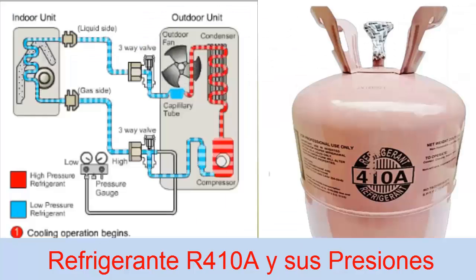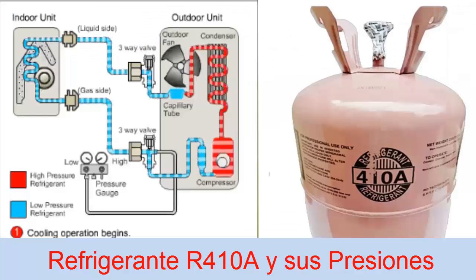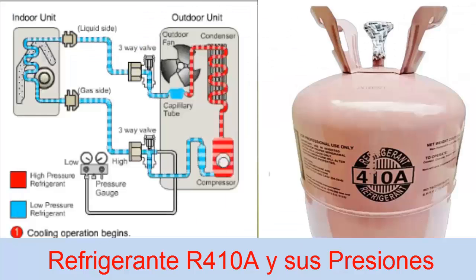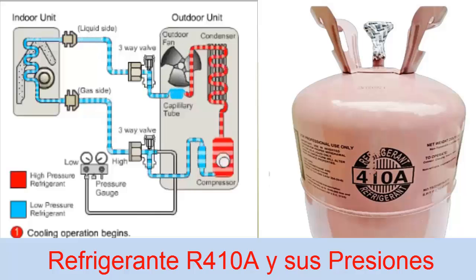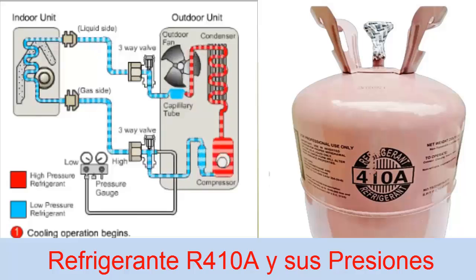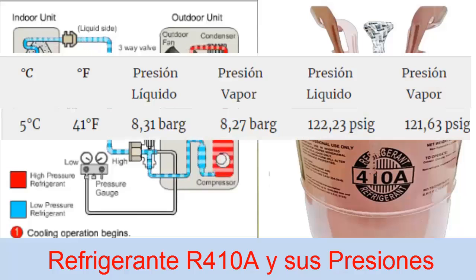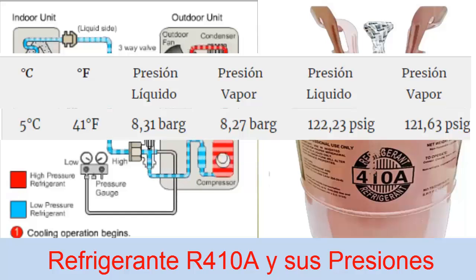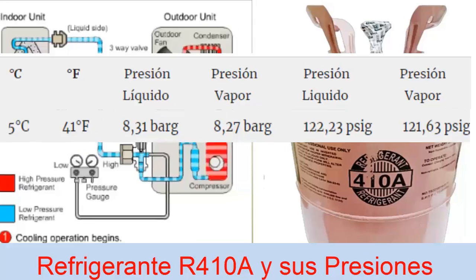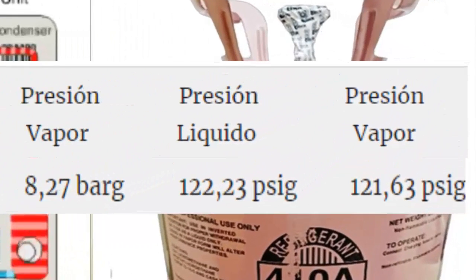In these equipment, the work temperature in the evaporator is about 5 degrees Celsius, about 41 degrees Fahrenheit. For this temperature value, the pressure in the evaporator that must mark the low pressure gauge with the equipment on is about 8.27 bar, or its equivalent of 121.63 psi — that would be the low side.